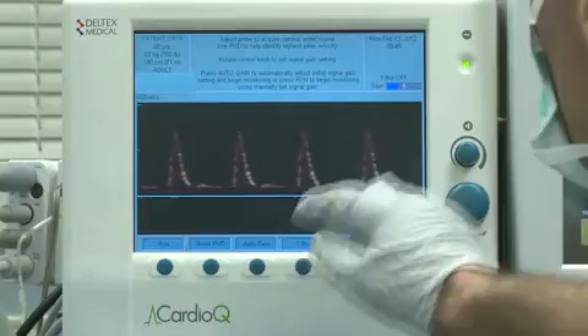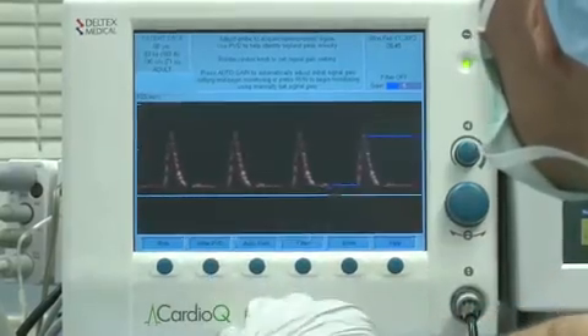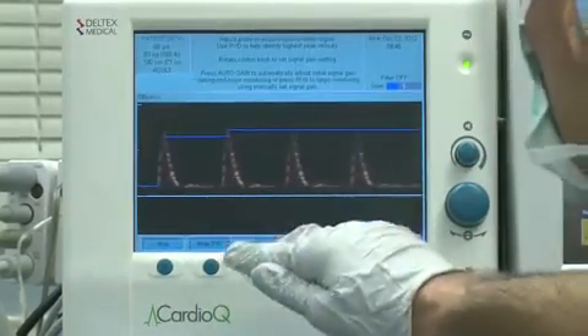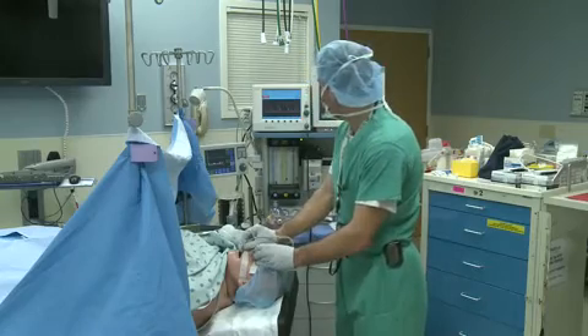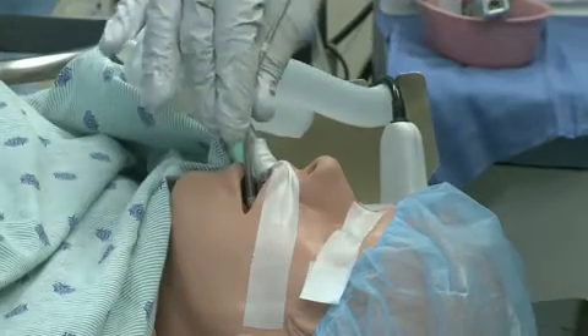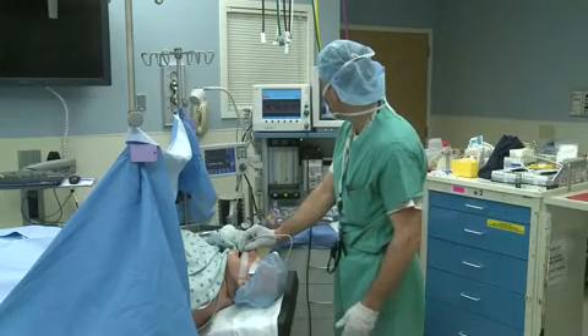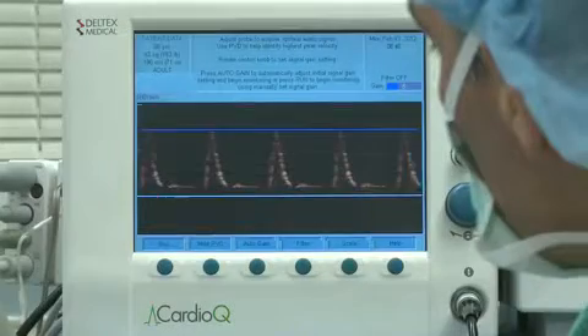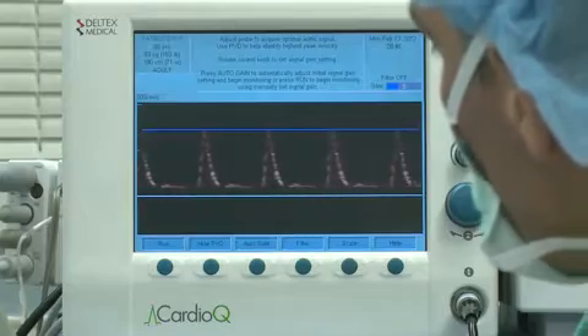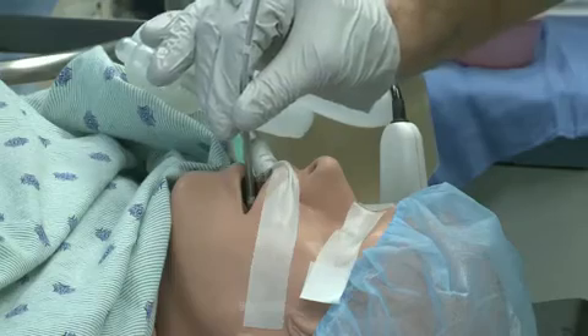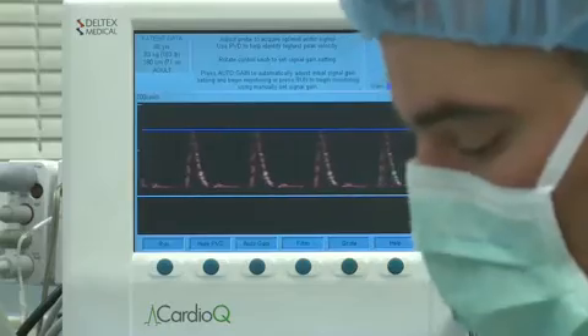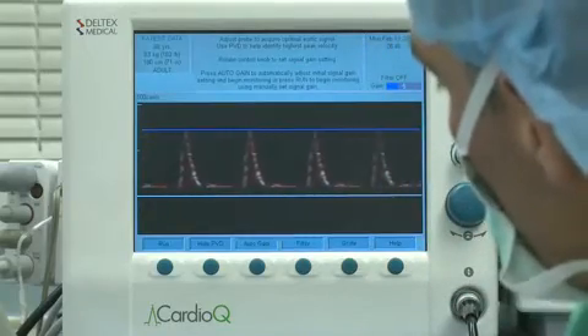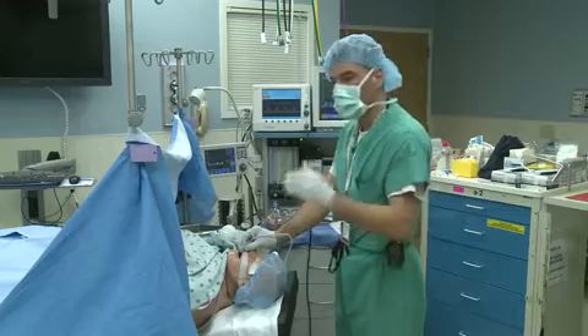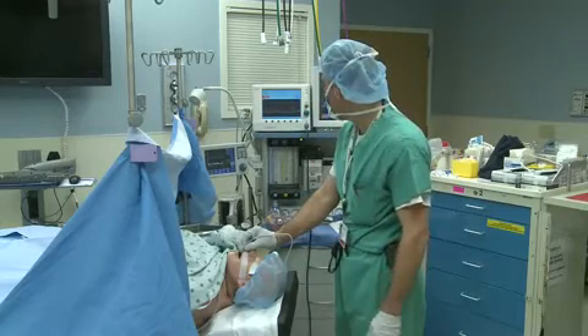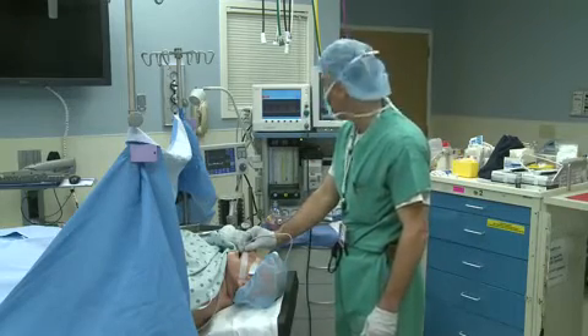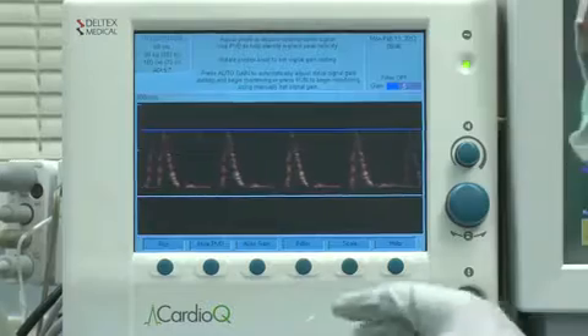So what we can do is hit the show PVD button, and then we can slowly twist the probe in through the mouth and just see where the best height is that we're obtaining, and you can see the blue line is tracing the height that you were at. So as you rotate the probe, you'll see the blue line either rising or falling depending on the signal. And so the best signal would be the highest point that blue line has, and that's your highest peak velocity. And so that's what you'll go for.